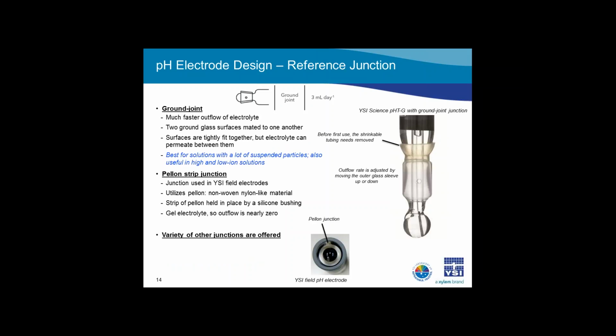However, for solutions with a lot of solids, low ionic strength, or high ionic strength, the ground joint junction is the best to use. This electrode junction features a much faster outflow of electrolyte, and it is very easy to clean. This junction, also known as the ground glass sleeve junction, features 2 ground glass surfaces mated to one another. These 2 surfaces fit tightly together, but they allow electrolyte to permeate between them. The outflow rate can be adjusted by moving the outer glass sleeve up or down.